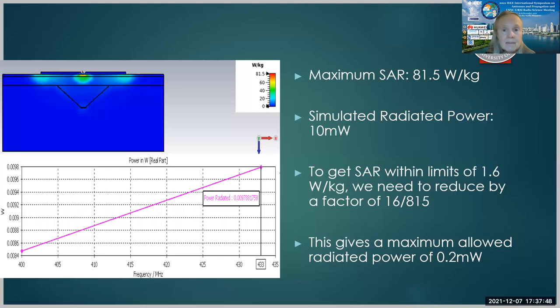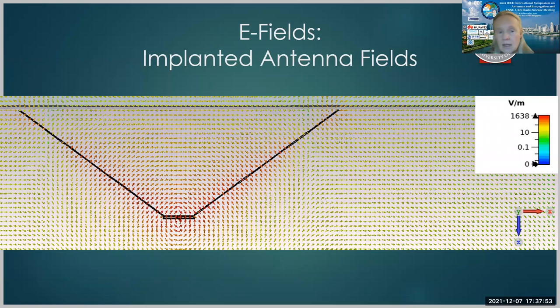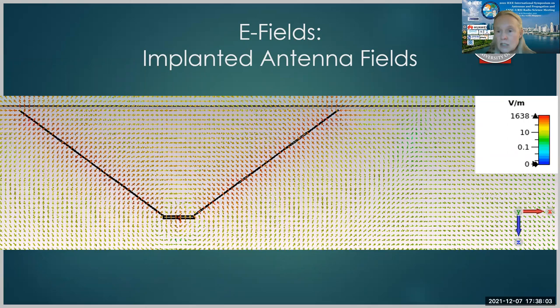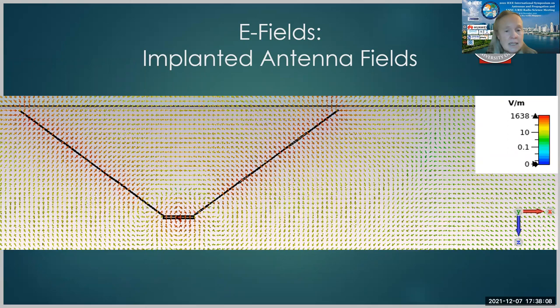And this is what the implanted fields look like. You can actually see how the rods are concentrating the energy. They actually are kind of picking it up and guiding it down the rod towards the implantable medical device. Now, remember, they are not touching directly. There is capacitive coupling or inductive. There's passive coupling to the medical implant and the rods are helping substantially.